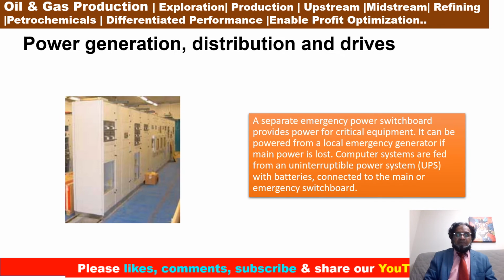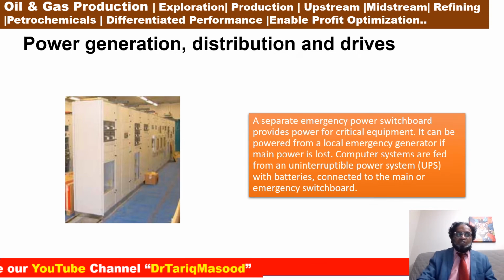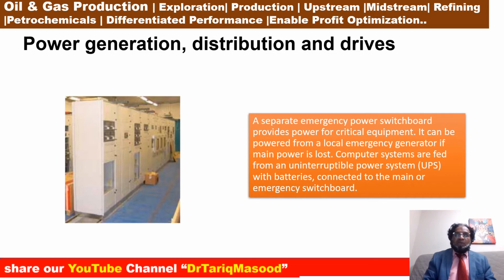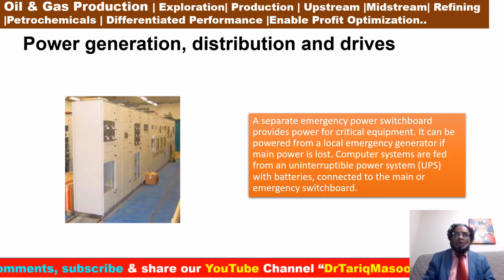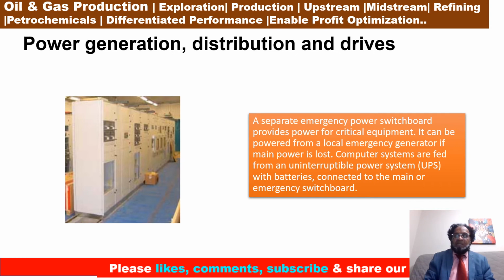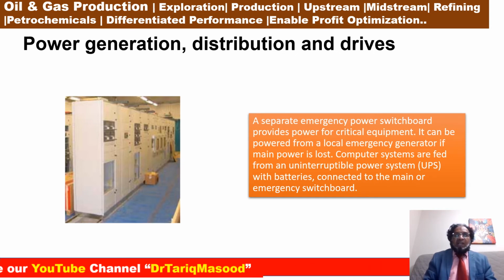Computer systems are fed from an uninterruptible power system, UPS, with batteries connected to the main or emergency switchboard. A power management system is used for control of electrical switchgear and equipment performance. Its function is to optimize electricity generation and usage and to prevent major disturbances and plant outages, blackouts. The power management system includes HV, MV, and LV switchboards plus MCC and emergency generators.